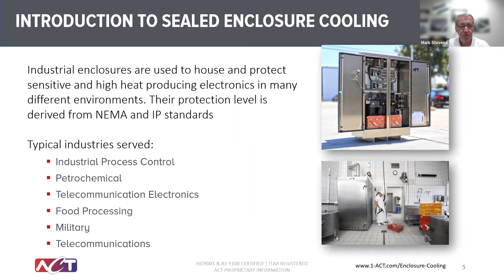Also, regarding environmental ratings, we have units that address NEMA 12, NEMA 4, 3R, and 4X. We've put together rough equivalents in IP ratings because there isn't any real direct rating. So we've done our best estimate on what a NEMA 12 is for an IP rating, which is 52. And if we talk about our 4X, it's probably pretty close to a 65 or 66. That's our best approach when trying to assess these products.